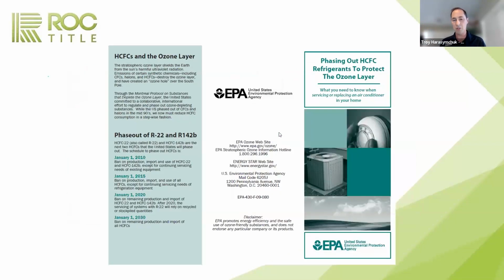So what ended up happening to R22? And if you have a rep here from Old Republic and you want this, I'll have the reps reach out to me and they can forward this information to you. This is the EPA document on R22. So if you notice here, just a couple dates. On January 1st of 2020, we stopped making R22 altogether. But I just want to bring out a small point here, because sometimes contractors will seize on that and use misinformation to sell a client a new unit prematurely. It's in small print, but I'm going to read it. It says ban on remaining production, but you can still use recycled or stockpiled quantities.